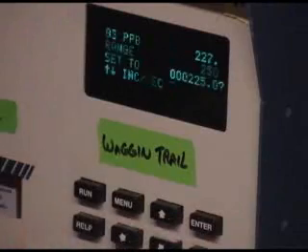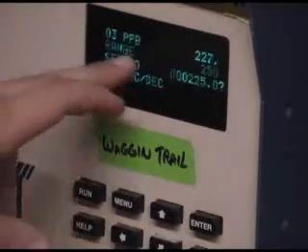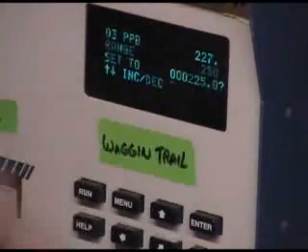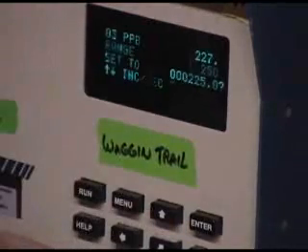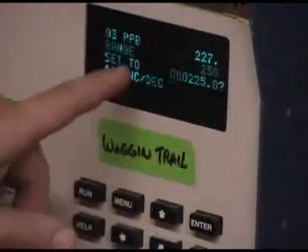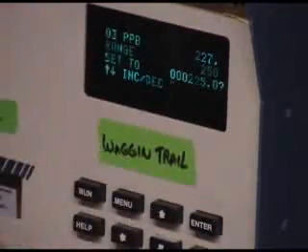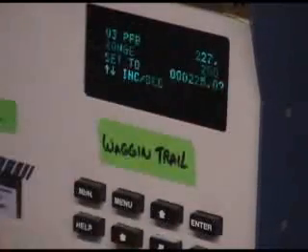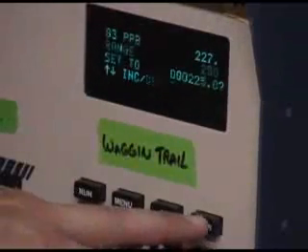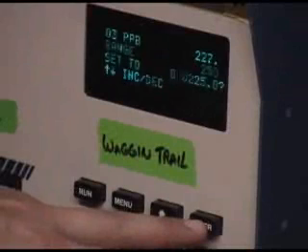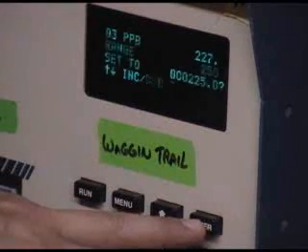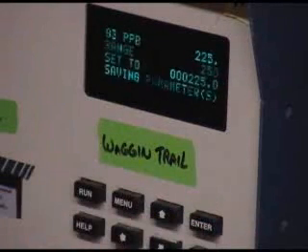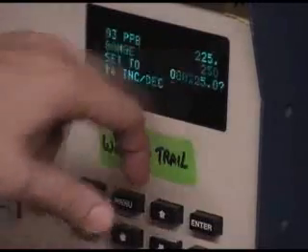I was here with ozone. Set to 225, it's already programmed in there. Our range is as high as 250. This is the reading we have right now. We want to set that to 225 because our calibrator is set for 225. So we'll hit enter. Save the parameters. You see it's changed it.